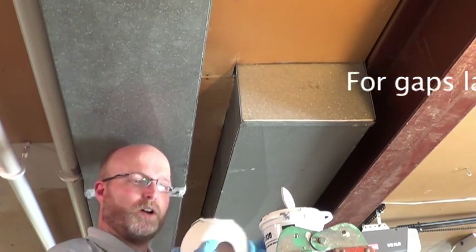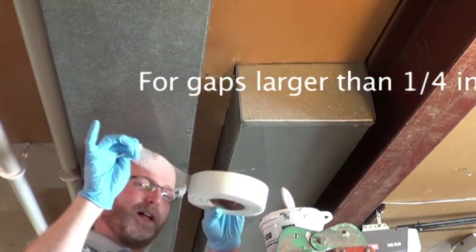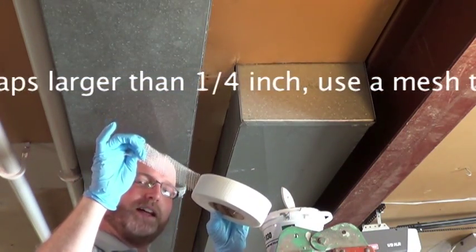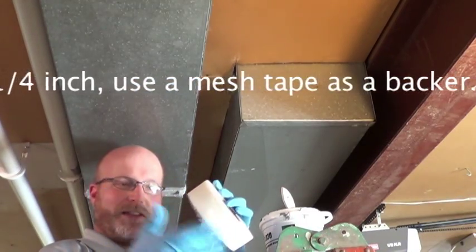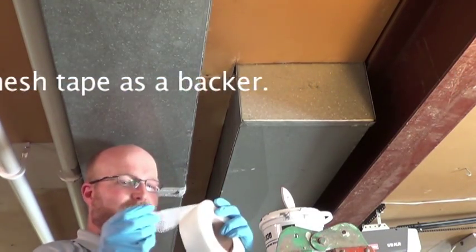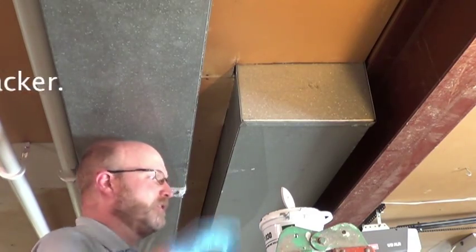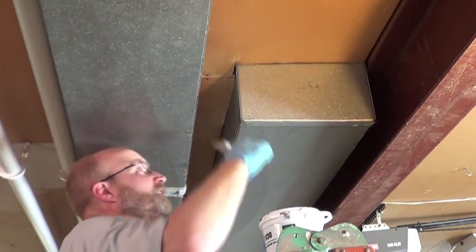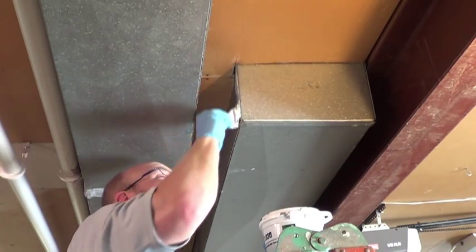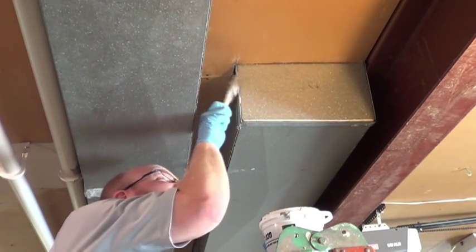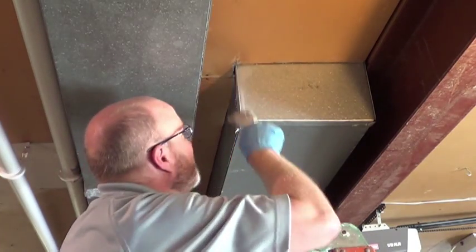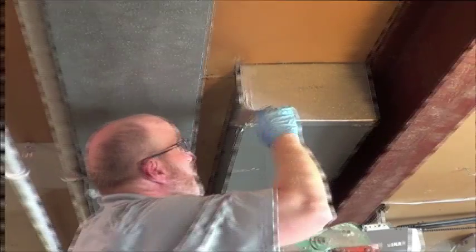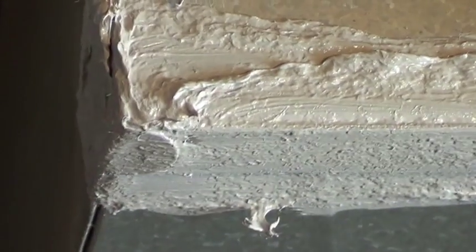If you have a gap that's wider than 1/4 of an inch, we're going to apply some of this mesh tape first over that gap, and then the mastic goes right on top of the mesh tape. So this provides a backer for, again, anything over 1/4 of an inch. So let's do some duct sealing. And we're going to go all the way around, of course. And eventually we will tackle all of these seams on the ductwork.